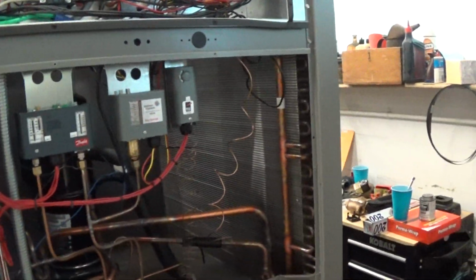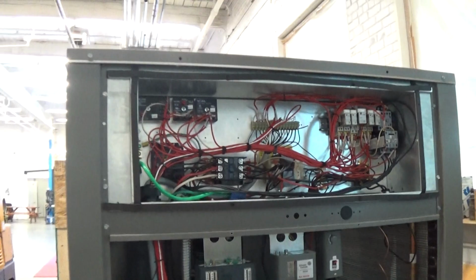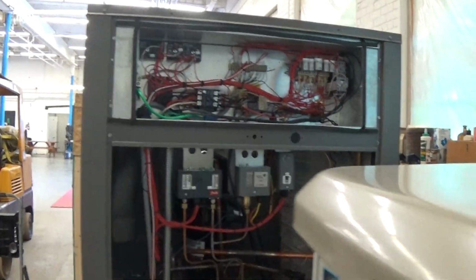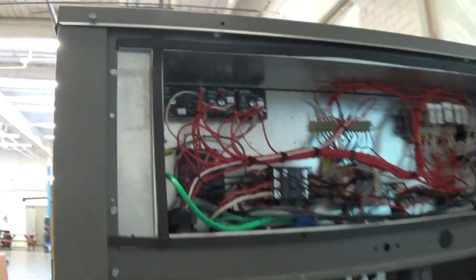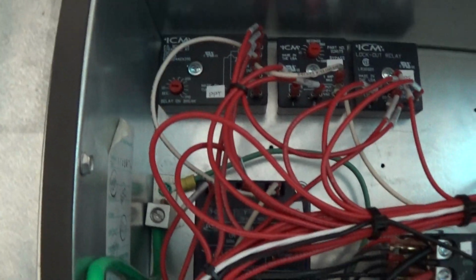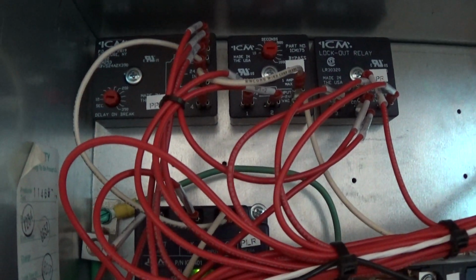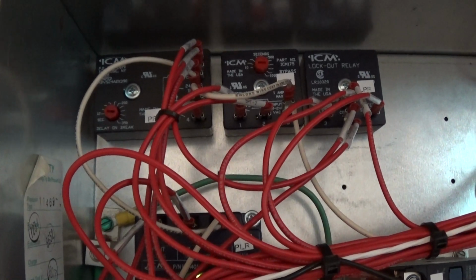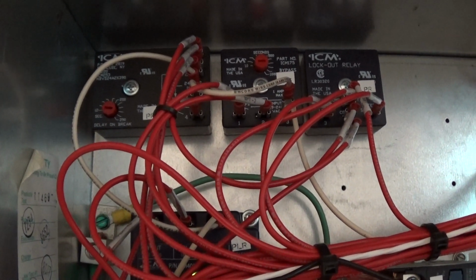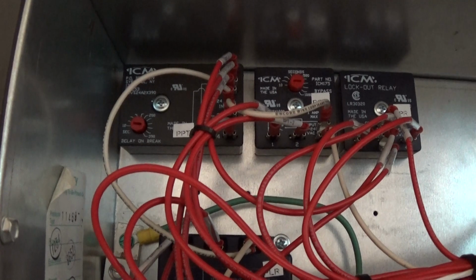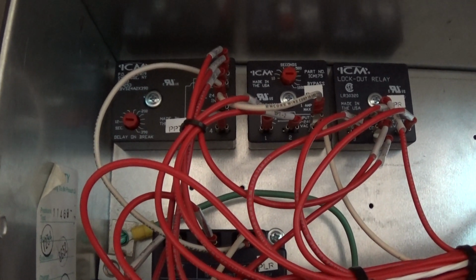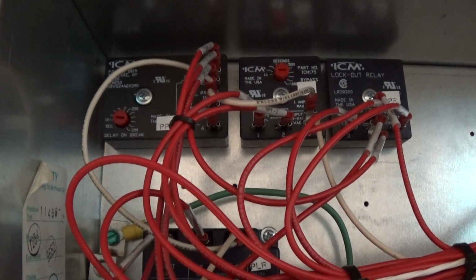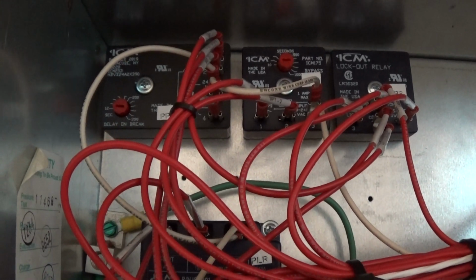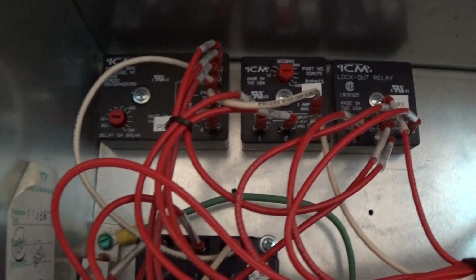A couple key things in the control cabinet we'll go over first, because this does have several nice features. In the top left corner here, you see a timer labeled a PPT. That's our off delay on break timer, or the post purge timer. I mentioned the pump down. That's there to allow the compressor to complete its pump down cycle after each on cycle.